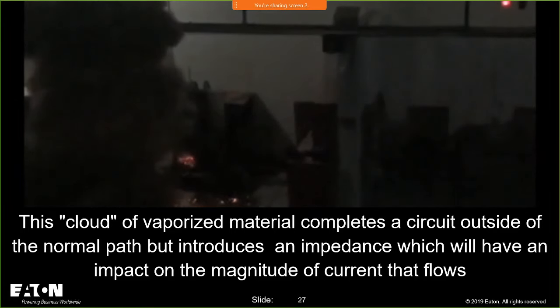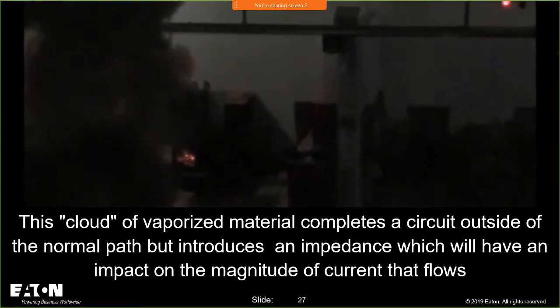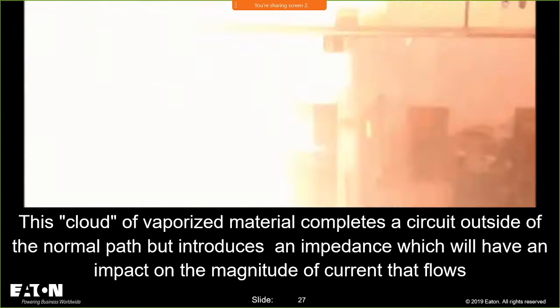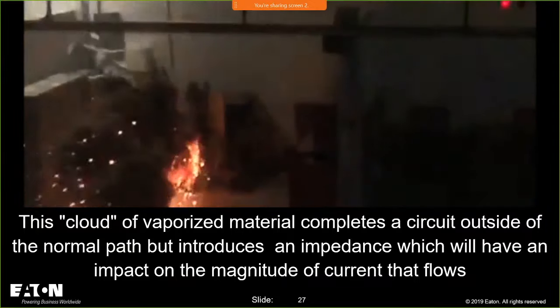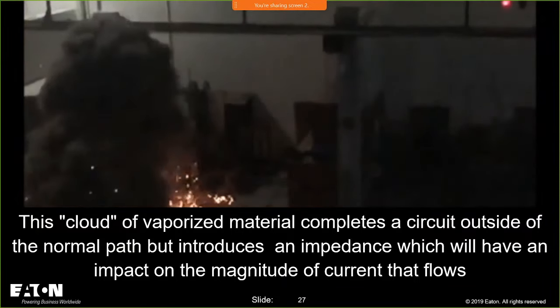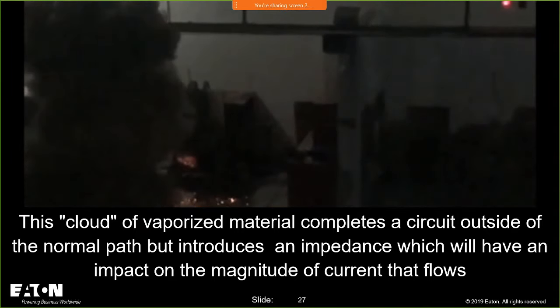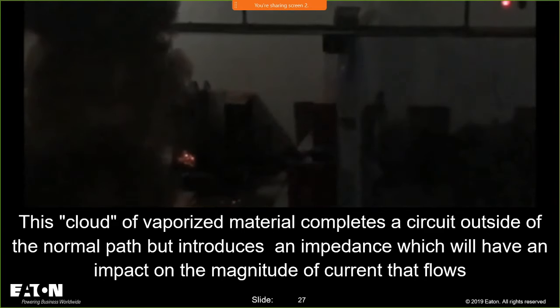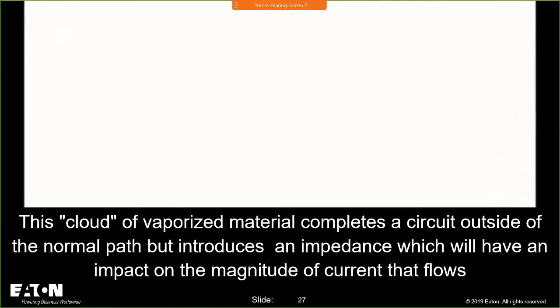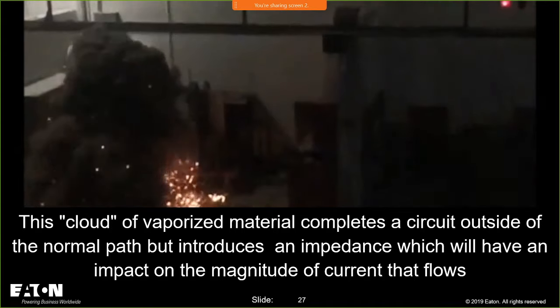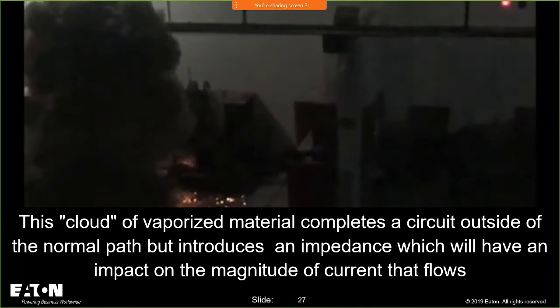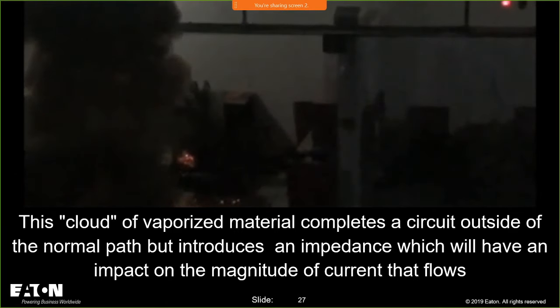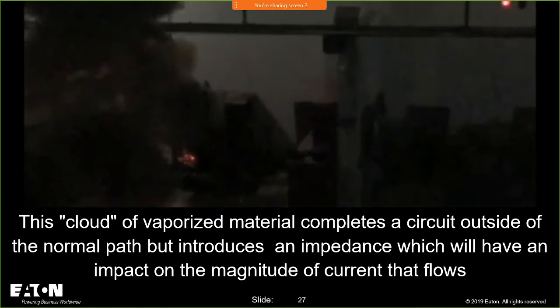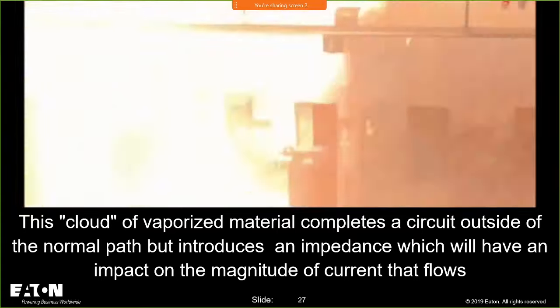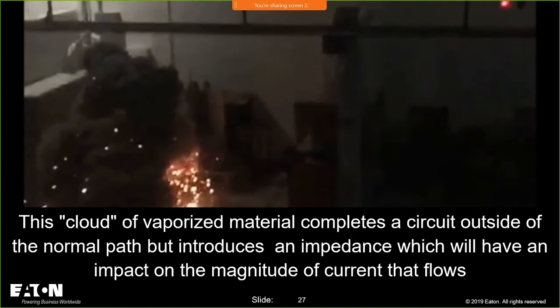But that plasma plume is going to generate a way for the current to flow outside of the normal path through the air, because it's energized, it's full of these particles that are conductive, but it adds resistance, it adds impedance into the system. And what that impedance does is it reduces the current. If I have 60,000 amps of bolted fault current available at this piece of equipment, when this explosion occurs and the current flows through the air, it's going to add impedance, it's going to reduce that current. When you add impedance into the system, it reduces the current. And that's why your arcing currents are always going to be less than your three-phase bolted fault current. Okay?